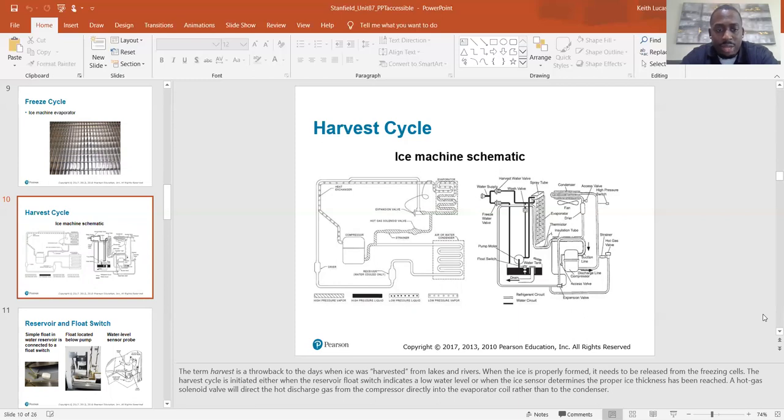A hot gas solenoid valve will direct the hot discharge gas from the compressor directly to the evap coil rather than to the condenser. So that would be right here. Normally the hot gas will go straight to the condenser coil, but for the defrost cycle, it's going to go differently.